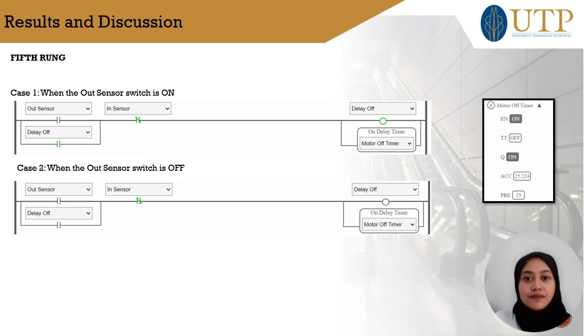The selection of an on delay timer in the PLC allows the timer to reset the accumulative value to 0 if the out sensor triggers again below the preset value. So when there is a passenger exiting the escalator, the second passenger will still have 25 seconds to exit the escalator without having the escalator turn off while the second passenger is still in the middle of the escalator.